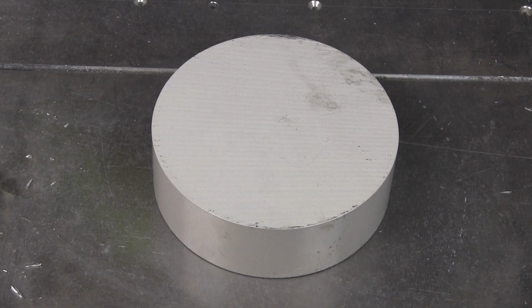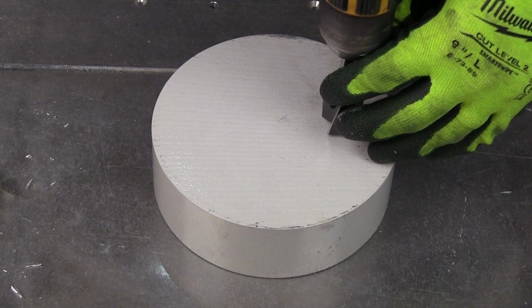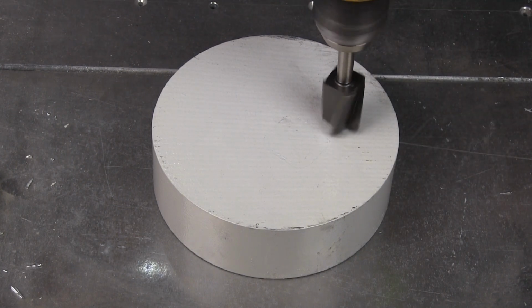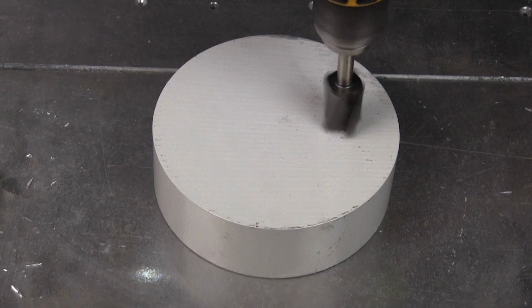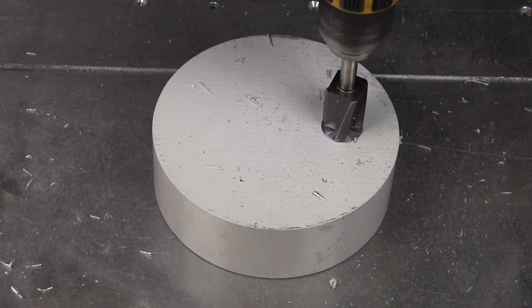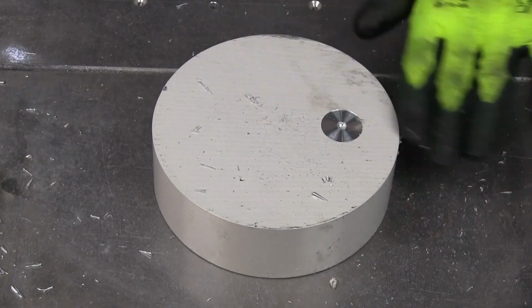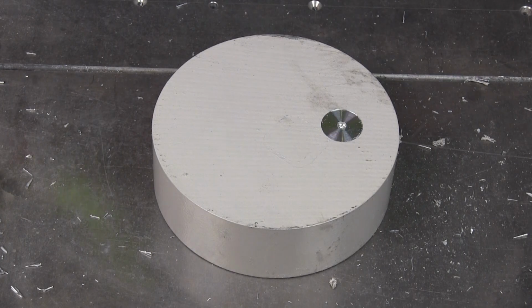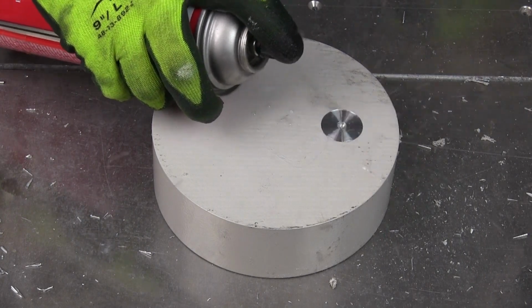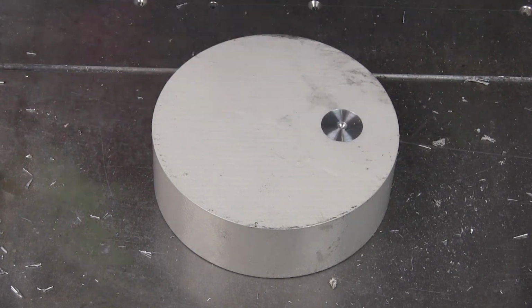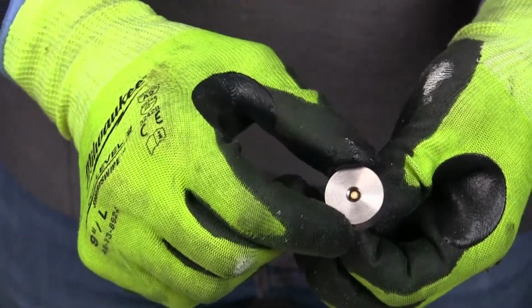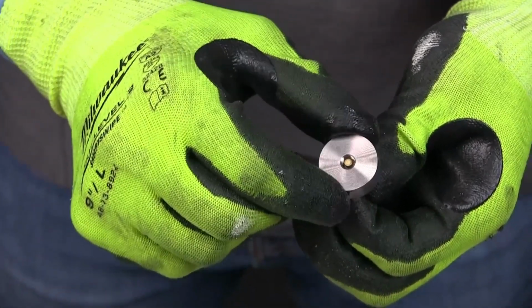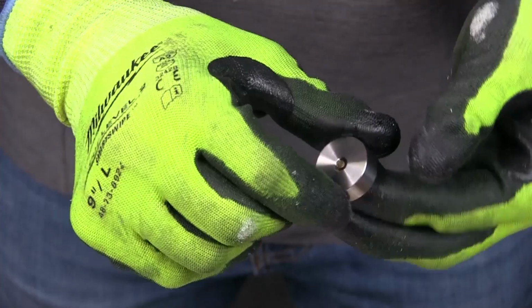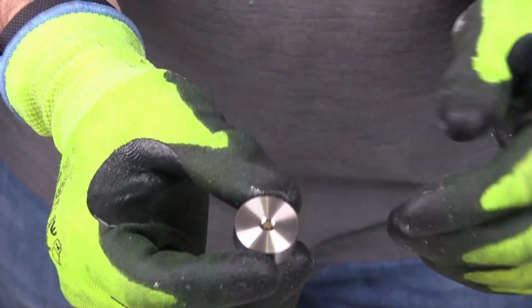When mounting via adhesive mounting pad, the spot face process is the same as when stud mounting. The paint and top layer of machine surface is shaved away with the spot face tool. In this case, the pilot hole is not used. The surface should be clean and free of debris. Putting a stud through the adhesive mounting pad before applying adhesive prevents the adhesive from flowing into the threads in the center of the pad.